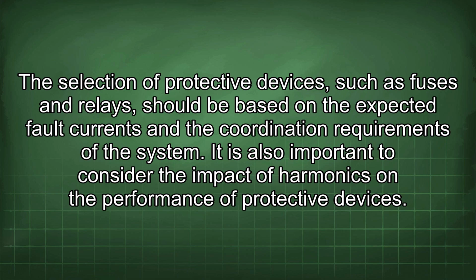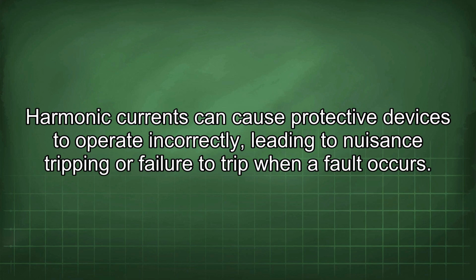It is also important to consider the impact of harmonics on the performance of protective devices. Harmonic currents can cause protective devices to operate incorrectly, leading to nuisance tripping or failure to trip when a fault occurs.